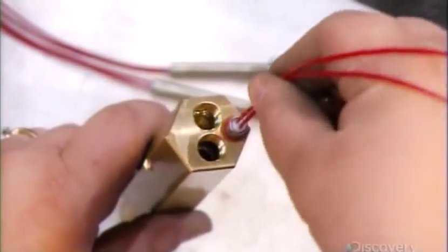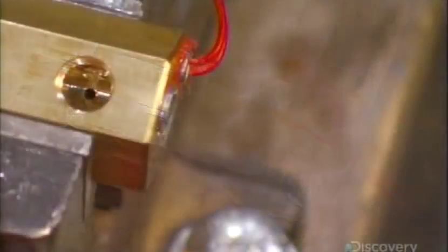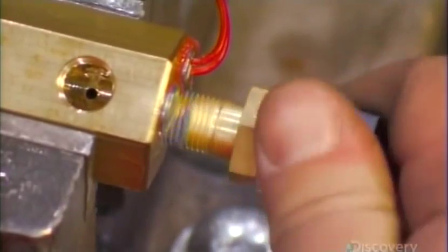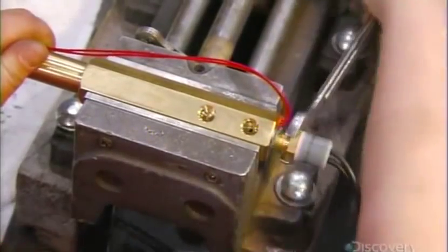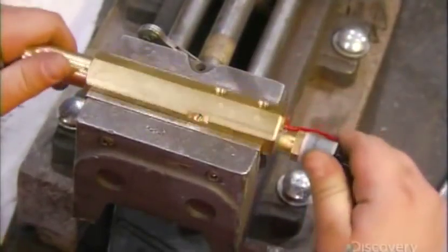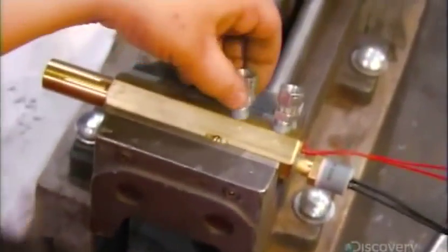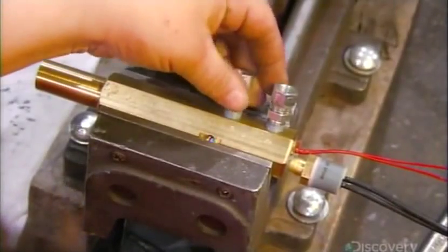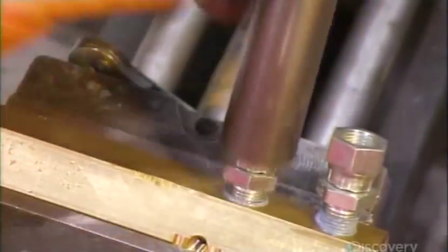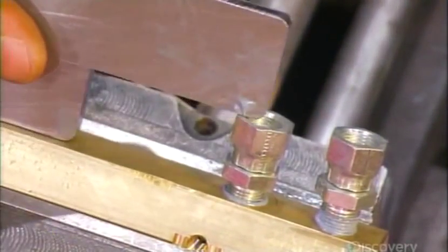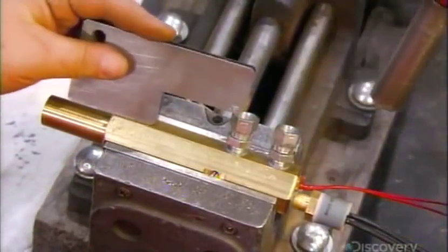A technician installs a 100-watt pencil heater inside a brass nozzle adapter, then threads a thermostat into it. This nozzle adapter heats the oil and turns it into a fine mist so it burns properly. She then attaches assembly fittings to the adapter so she can later mount it inside a burner housing. She checks these fittings with a leveling tool to ensure the adapter will go on straight inside the housing.